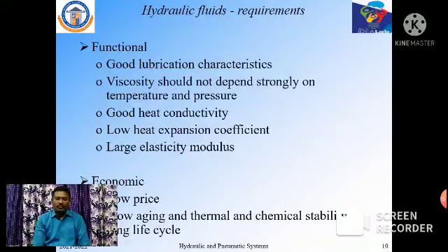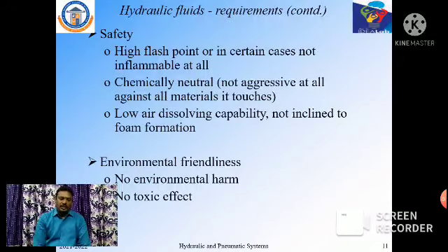Hydraulic fluid requirements. Functional: good lubrication characteristics, viscosity that does not depend strongly on temperature and pressure, good heat conductivity, low heat expansion coefficient, and large elasticity modulus. Economics: low price, slow aging, thermal and chemical stability, and long life cycles. Safety: high flash point or, in certain cases, not inflammable at all. Chemically neutral, not aggressive against materials it touches. Low air dissolving capability, not inclined to foam formation. Environmental friendliness: no environmental harm and no toxic effects.